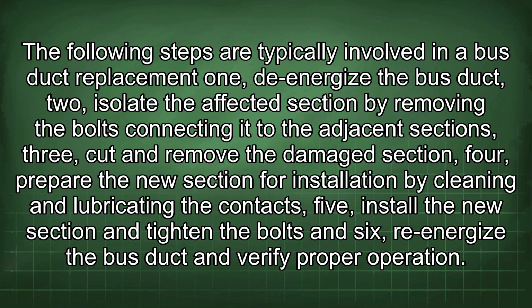1. De-energize the bus duct. 2. Isolate the affected section by removing the bolts connecting it to the adjacent sections. 3. Cut and remove the damaged section. 4. Prepare the new section for installation by cleaning and lubricating the contacts. 5. Install the new section and tighten the bolts. And 6. Re-energize the bus duct and verify proper operation.